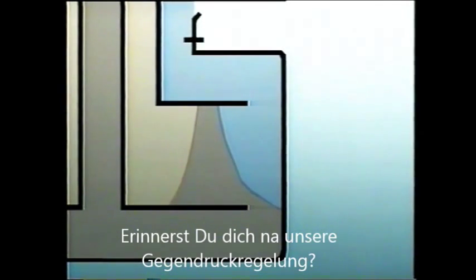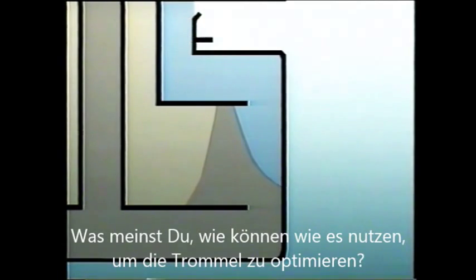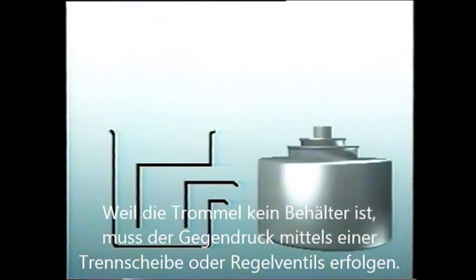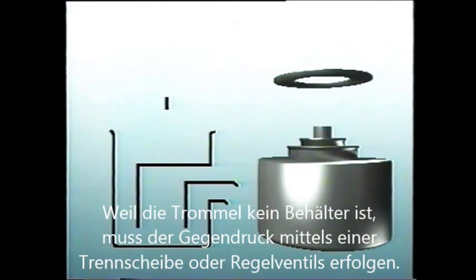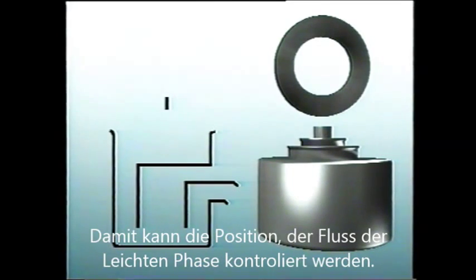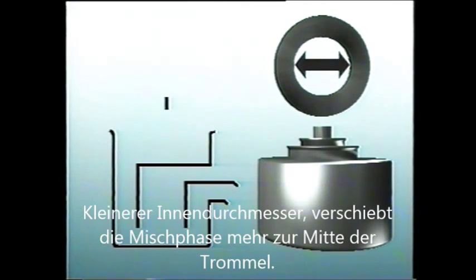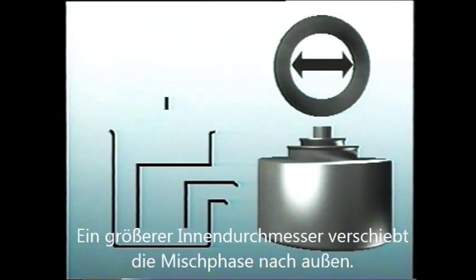How do I capture the loose lighter globules and control the interface, keeping it where we want it? Remember the dam or weir in our balanced column tank? Because the tank is now a bowl, the dam must become a ring. This is called a gravity disk — a sort of restricting ring by which we can control the position of the interface. A smaller inner diameter in the disk moves the interface towards the center; a larger inner diameter moves it outwards.